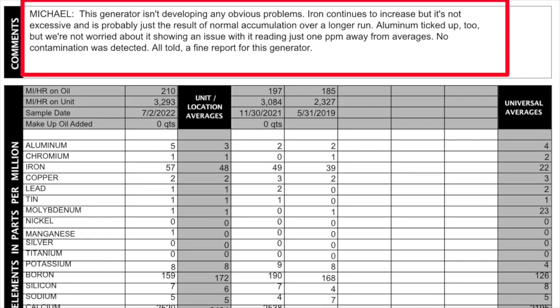On the July 2nd, 2022 report, iron went up another almost 10 points to 57. The comments read: 'Michael, this generator isn't developing any obvious problems. Iron continues to increase, but it's not excessive — it's probably just a result of normal accumulation over a longer run. Aluminum ticked up too, but we're not worried about it showing an issue with it reading just one part per million away from the averages. No contamination was detected. All told, a fine report for this generator.' So even though the number was going up, their comments really helped get me more comfortable with the readings.